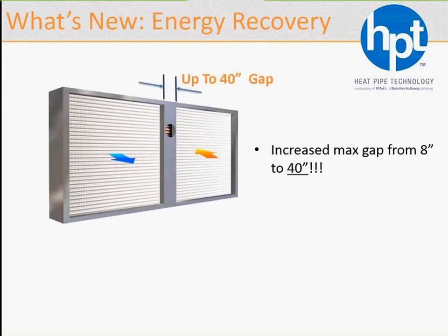So what's new with this product? The gap. And if you'd used this product before, the gap used to max out at about 8 inches. Now we can go all the way to 40 inches. That gap can be filled with polyurethane that expands and fills that gap, or in lesser contaminated environments or lower class airs, if you like, that gap can stay basically full of air. A little contamination will take place. Our product under testing actually shows practically zero cross-contamination between airstreams. It is always advisable to fill that gap with polyurethane, and that's an adder that's available in our selection program.